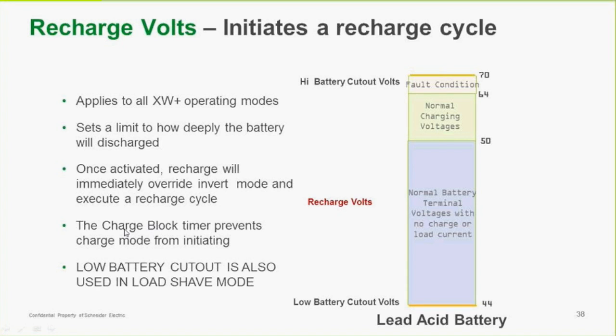You can set a charge block timer. If the batteries are run down and the charger is calling to charge them, but you're in the middle of the day when electrical rates are the highest, you can block out that time, and it'll wait till that time has expired and then go about charging the batteries when utility rates are much lower.